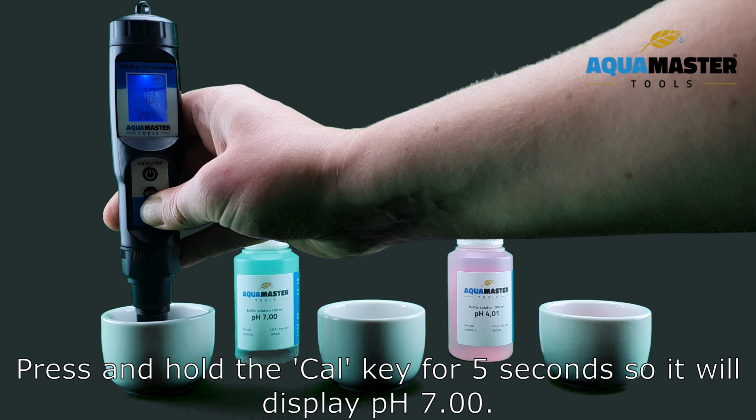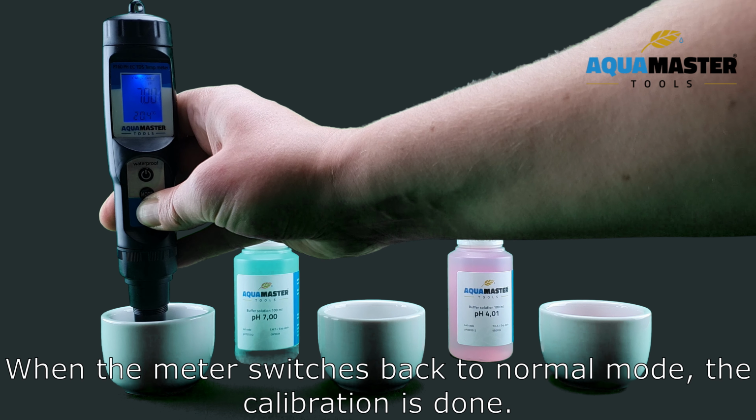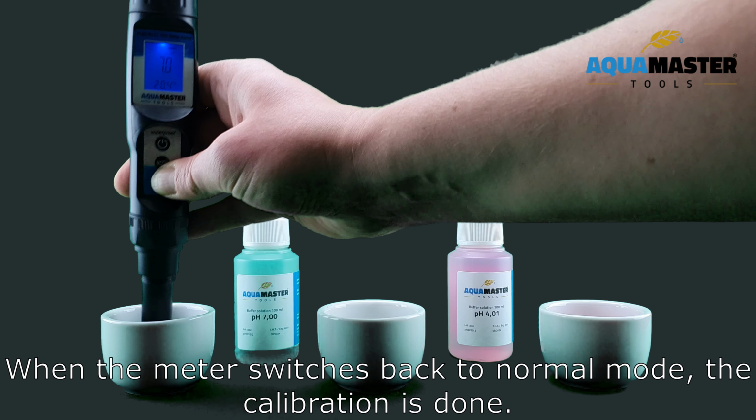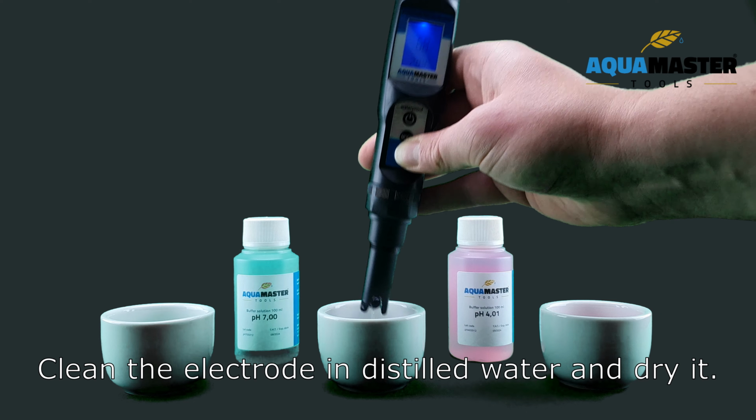Press and hold the cal key for 5 seconds so it will display pH 7.00. The meter is now calibrating. When the meter switches back to normal mode, the calibration is done. Clean the electrode in distilled water and dry it.